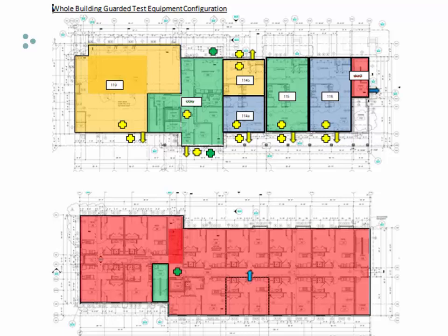We also needed to guard against the first floor commercial space for all of our single unit exterior leakage tests on the first floor to ensure we weren't measuring any leakage between the commercial space and those units. Because the protocol for this project requires new baselines for each measurement, that meant somebody had to be outside capping and uncapping each of these first floor commercial space blower doors for every measurement that we did.